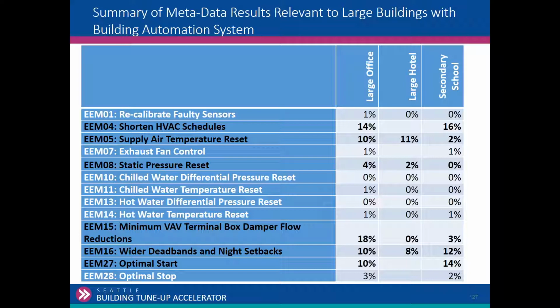Static pressure reset for VAV systems, if they're capable of doing that with VFDs. VAV minimum box position. I was talking to the PNNL folks, and I was very interested in how they discovered this and what they looked at in large offices. What they would see is a lot of VAV boxes where the minimum flow was greater than 30%. That's a lot on a VAV box. So that was kind of a red flag.